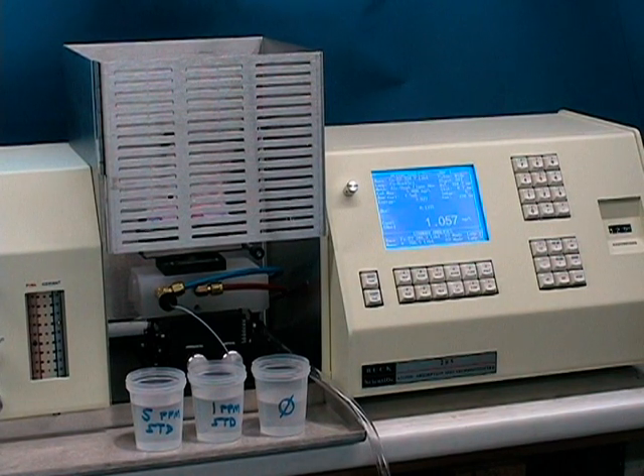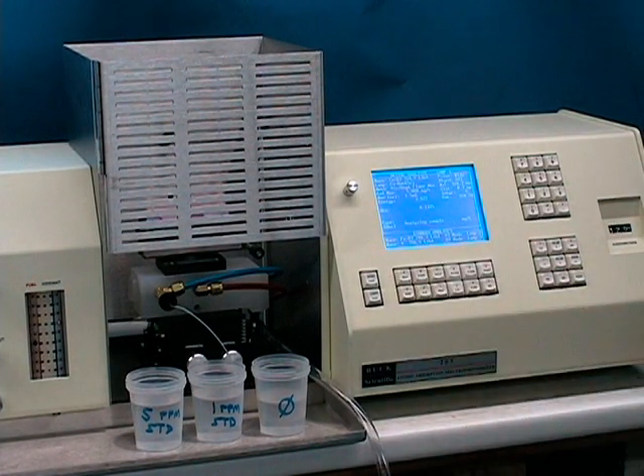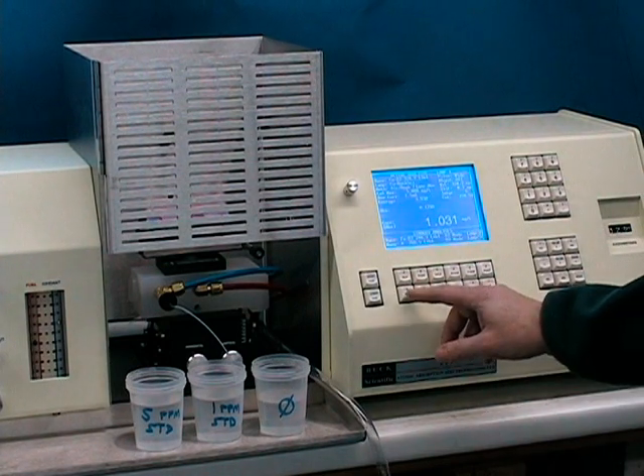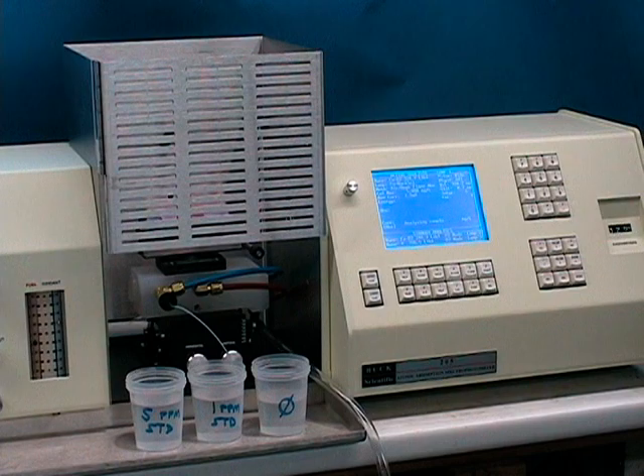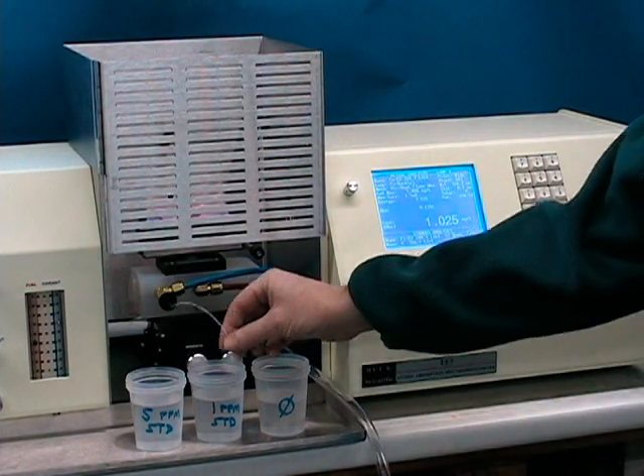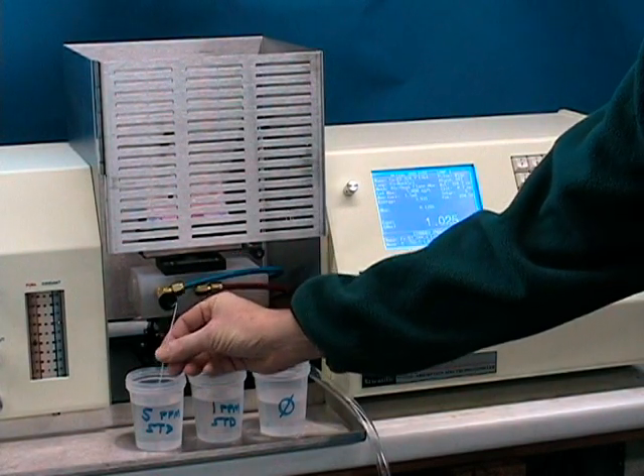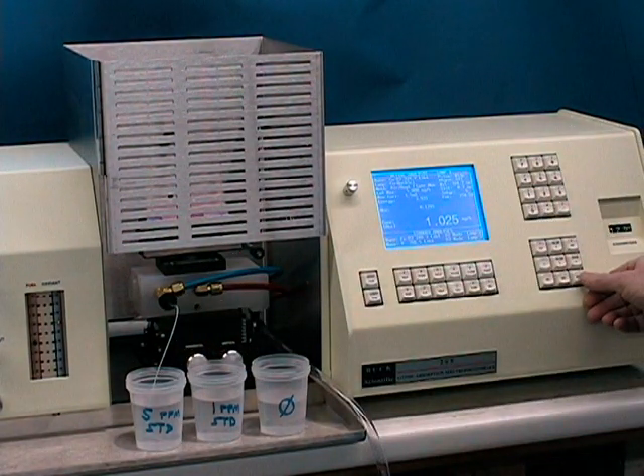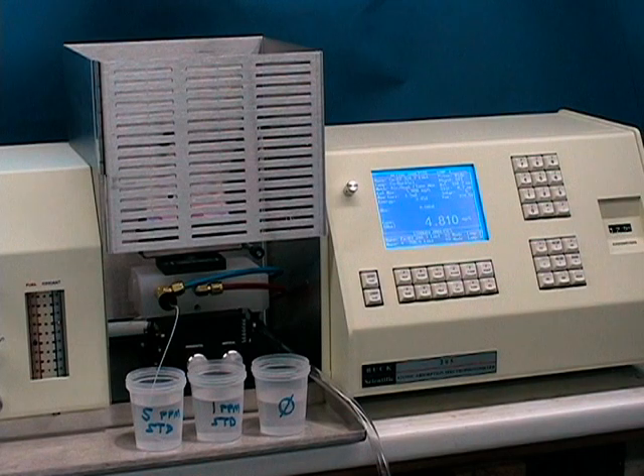For most flame AA work, you'll aspirate your sample or standard, press the read key to take an integrated reading as opposed to looking at the real-time jumpy readings. A relative standard deviation of plus or minus 5% is completely acceptable for most flame AA work. If any of your standards are outside of range, you can go ahead and do a recalibration by pressing the cal key and repeating that procedure.